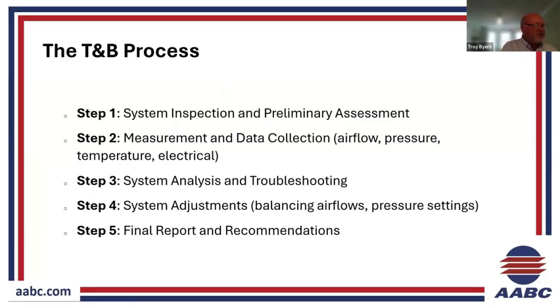So let's talk about the test and balance process. If you're a TAB professional, you know this process. This is how you approach all of your projects, by starting with the system inspection, the preliminary assessment, which is measurement and data collection. And we talked about some of those specific airflow, pressure, and temperature measurements that we're getting to determine capacities. The system analysis is where we're looking at those control strategies that are currently in place, and then contemplating control strategies that we could perhaps add or implement, troubleshooting to determine if something's not working properly, and then we start making system adjustments to get airflows to design. I want to pause right there because you can't go to step 4 if you need new design calculations. The TAB professional is not expected to make those calculations.